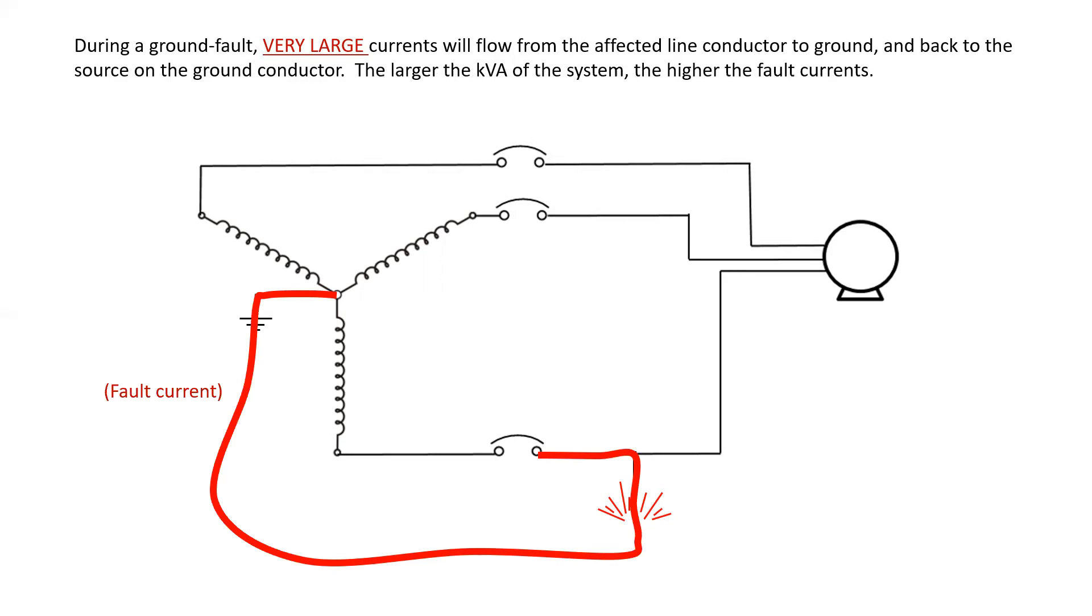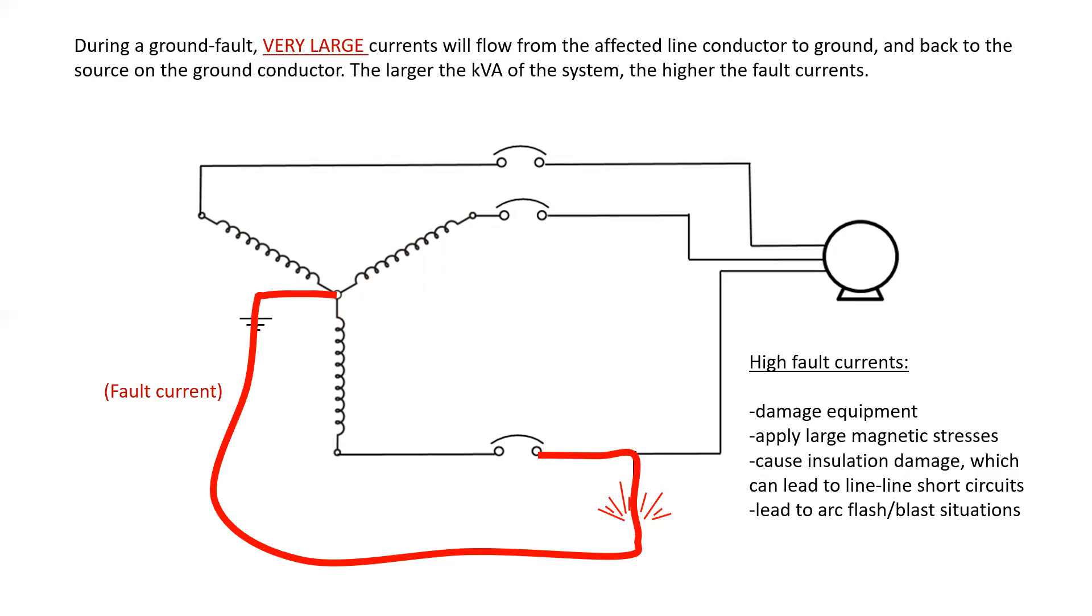The larger the kVA of the system, however, the higher the fault current values will be. And even though the breaker will trip, we're still going to result in some damage to equipment, and that can sometimes be in the form of thermal damage or in magnetic stress damage by bending and warping of equipment due to the current. We can also have insulation damage, which can lead to line-to-line short circuits and arc flash or arc blast situations.